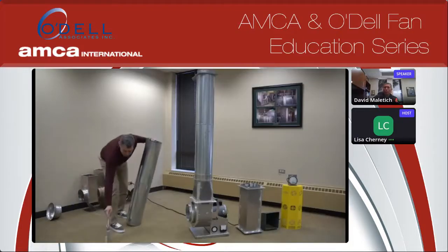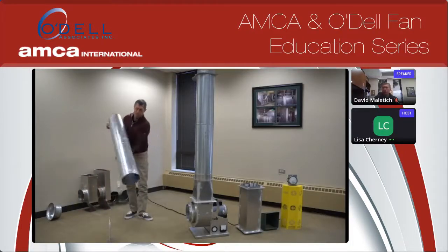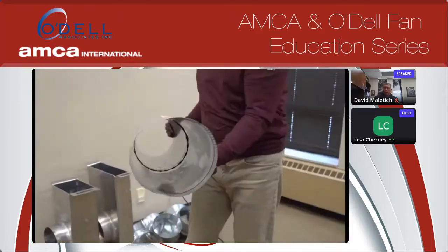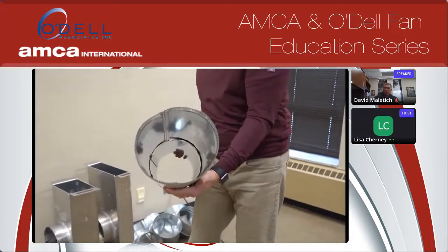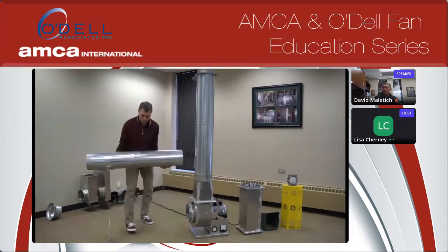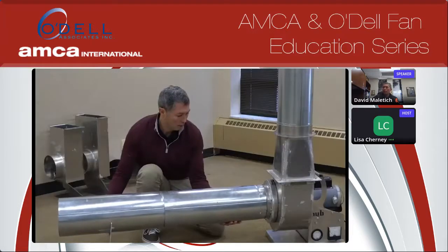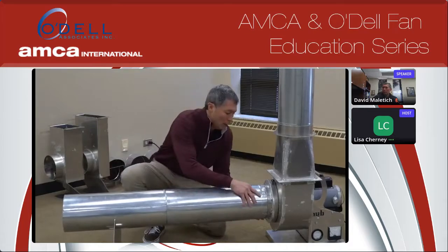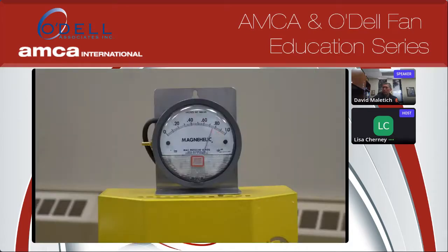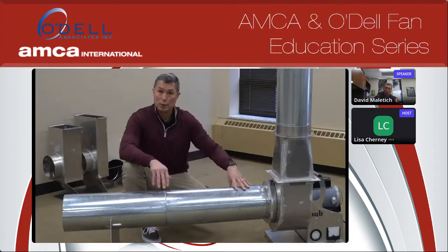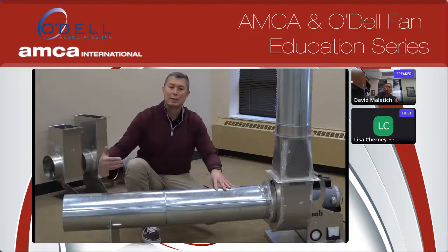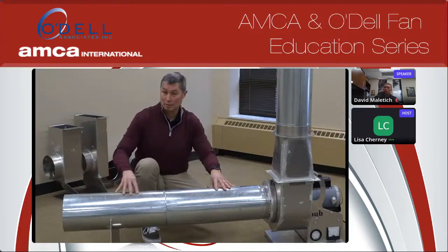And it's just a straight run of ductwork. You can see that it's just a long tube, and there's nothing inside of the tube, just a very hollow piece, and we're going to see what happens. Putting this on the fan, you'll notice that there's a loss associated with this straight run piece of ductwork, and that loss is actually relatively significant. Now, a lot of people think that that's associated with friction loss through this ductwork, the amount of effort that it takes to pull air over a piece of sheet metal or a piece of Schedule 40 pipe.